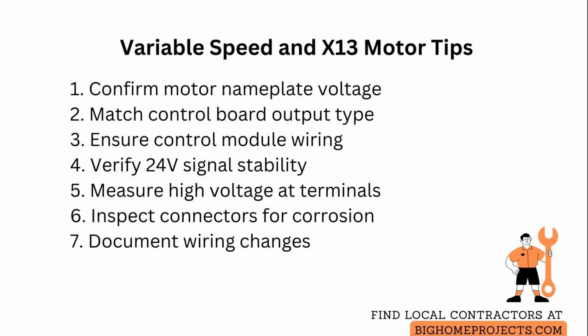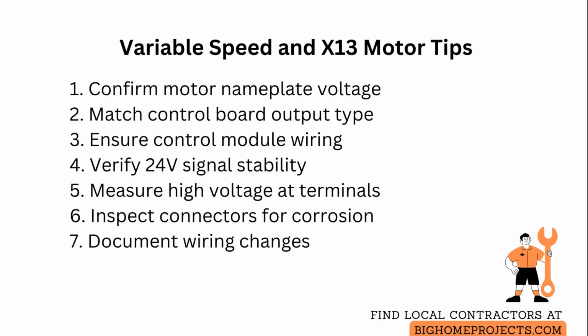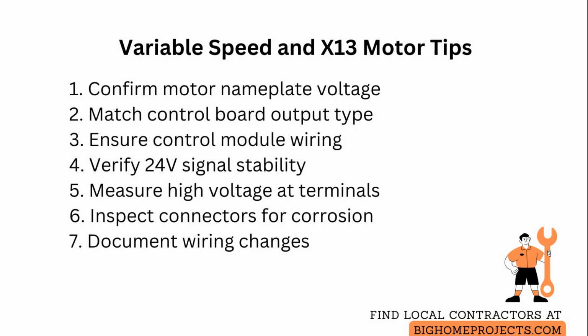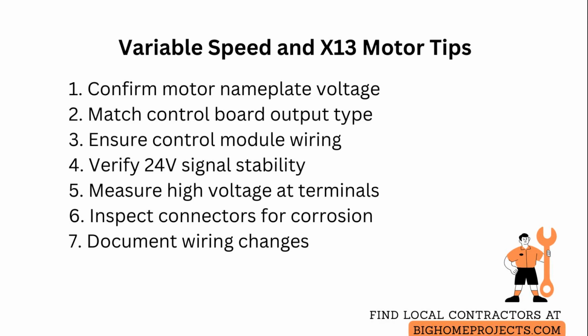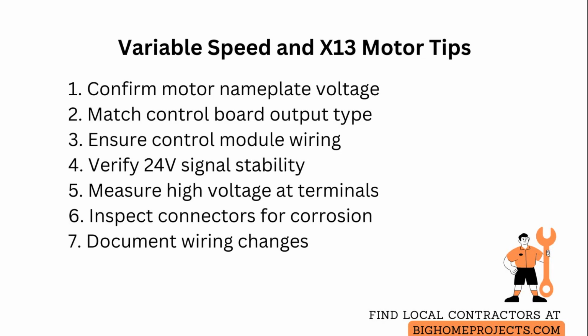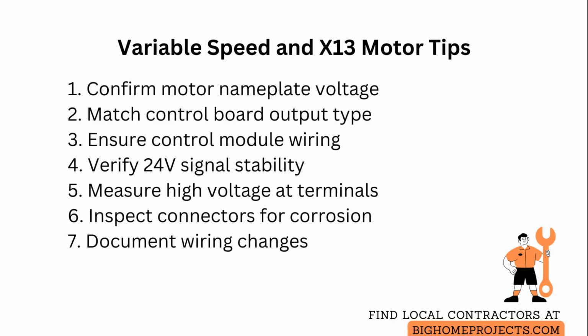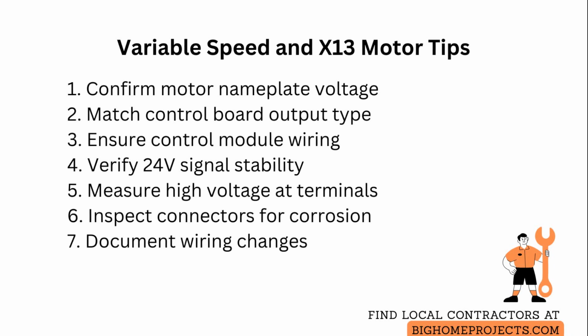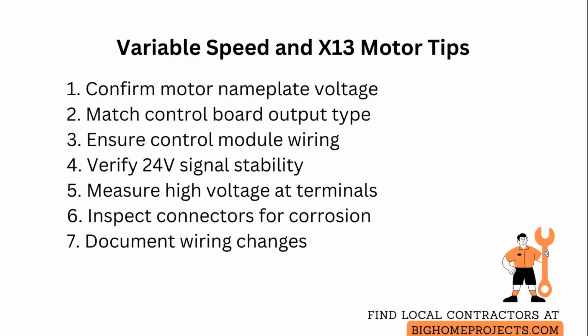X13 motors, sometimes called brushless permanent magnet motors, are designed to stay energized with high voltage but remain idle until a low voltage control signal commands them to start, so always verify the 24-volt control circuit is present, continuous, and free of noise or intermittent drops.